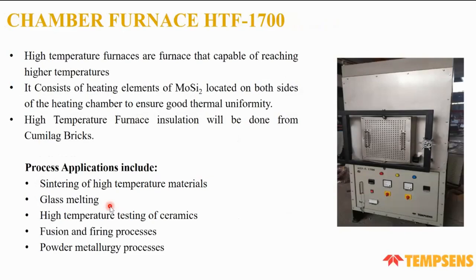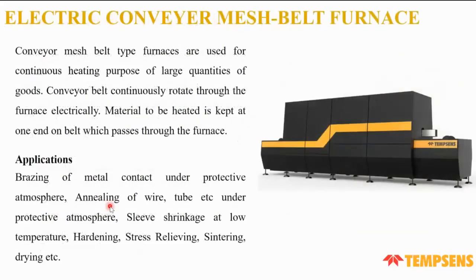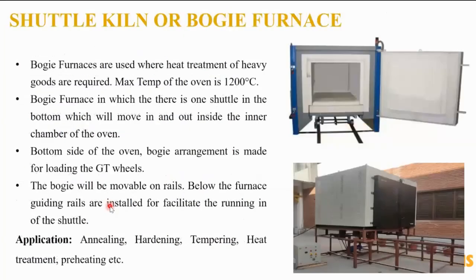The electric conveyor mesh belt furnace has a large heating zone with a continuously rotating conveyor belt for large quantities of goods. It can be used for annealing of tubes under a protective atmosphere. The bogie furnace operates at 1,200°C and uses a rail mechanism allowing the load platform to move backward and forward. Applications include annealing, hardening, tempering, heat treatment, and preheating.